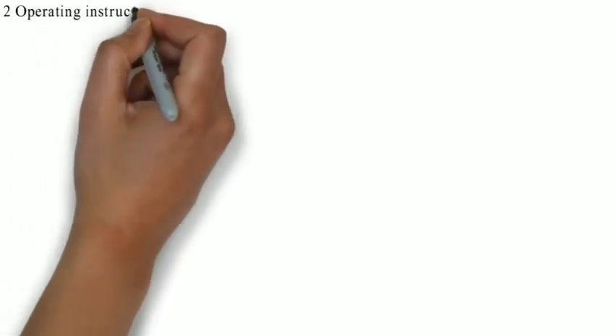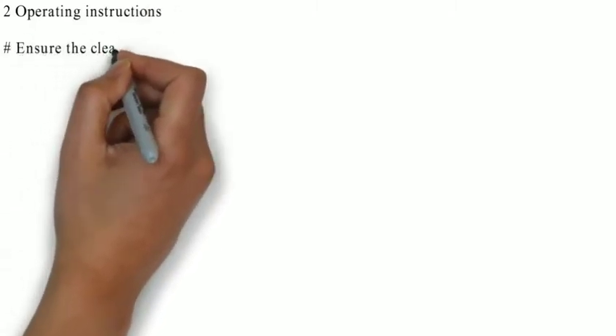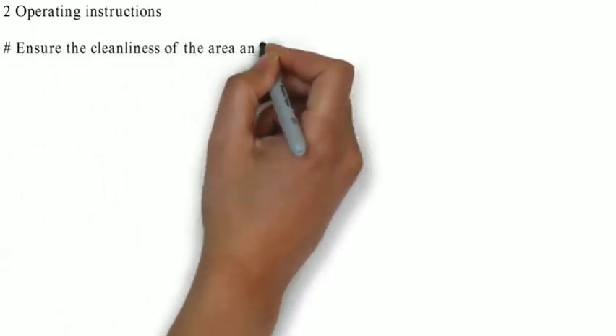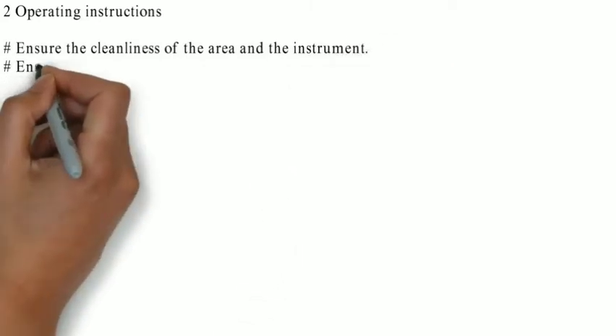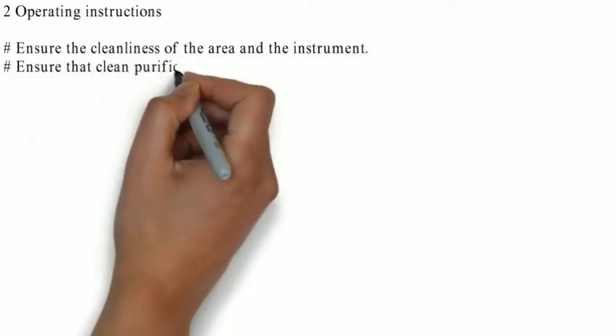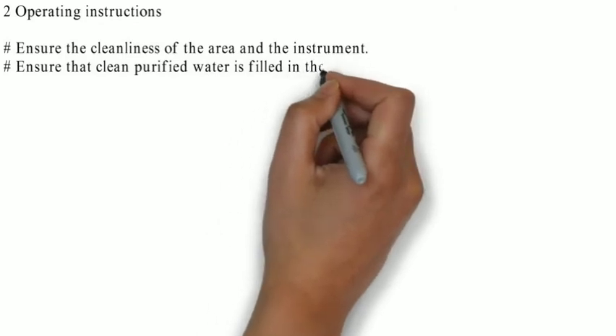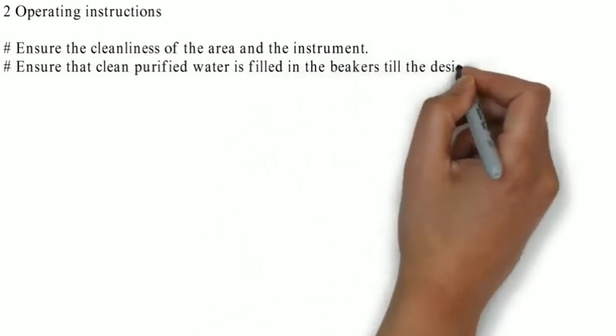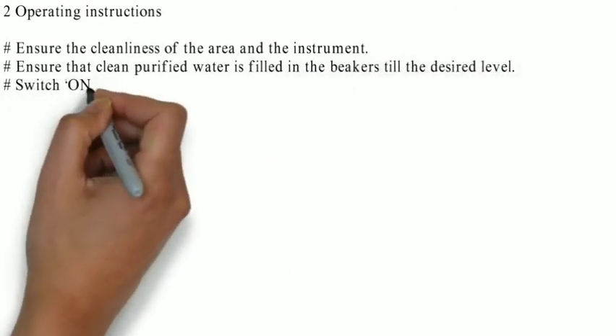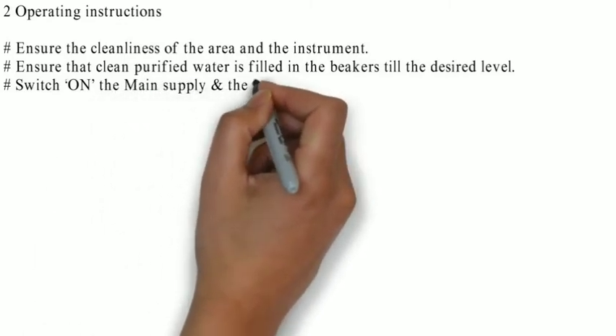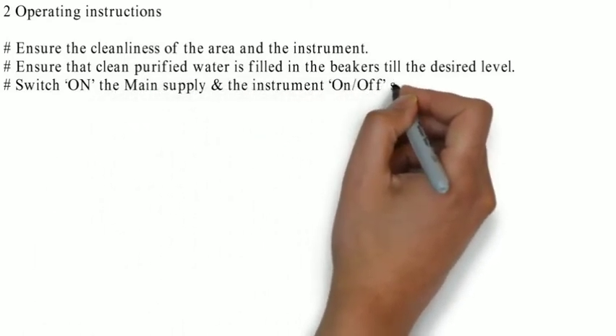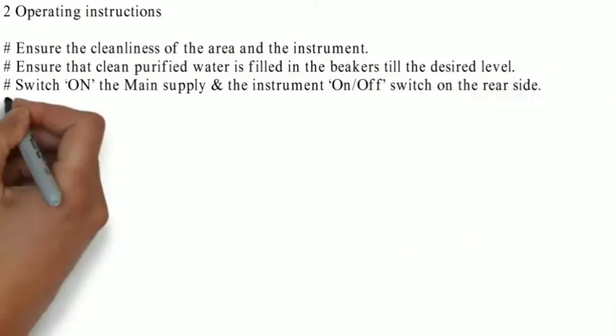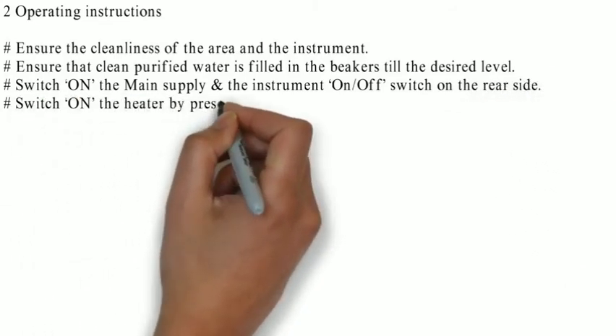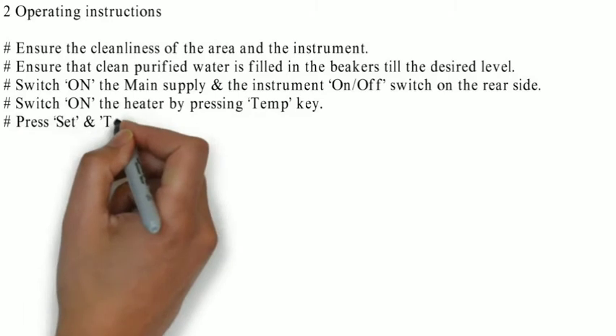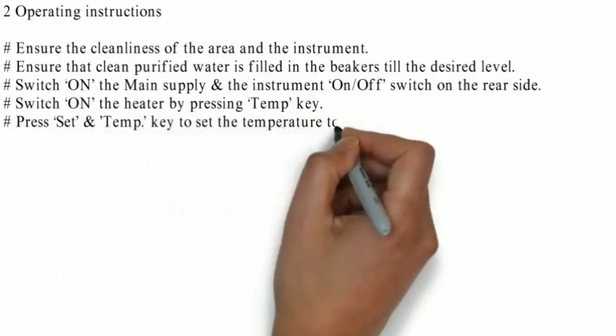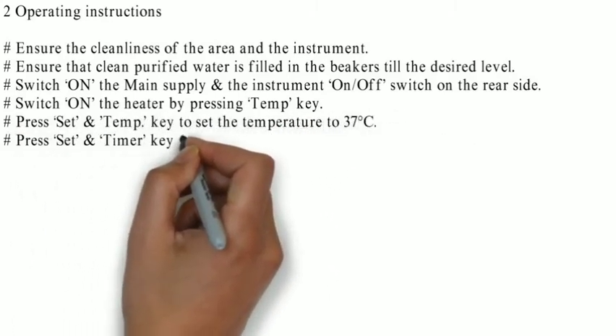Operating instructions: ensure the cleanliness of the area and the instrument. Ensure that clean purified water is filled in the beaker up to the desired level. Switch on the main supply, the instrument on/off switch on the rear side. Switch on the heater by pressing the temperature key. Press set and the temperature key to set the temperature up to 37 degrees Celsius. Press set and the timer key to set the desired test time.